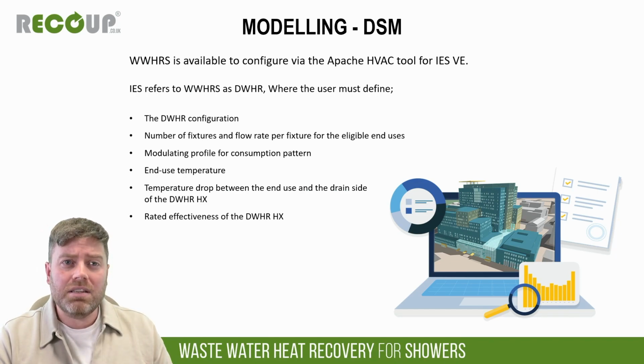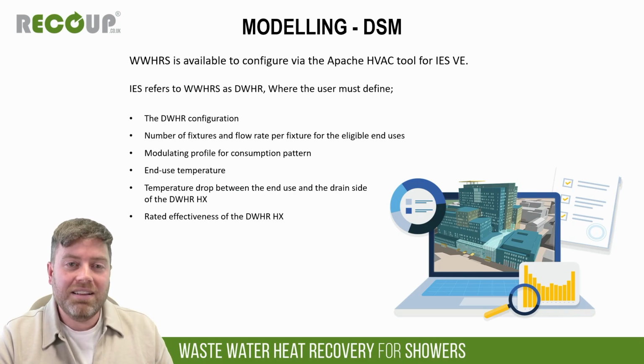In there, you need to specify the number of fixtures and flow rate per fixture for the eligible end uses, the modulating profile for consumption pattern, end use temperature, the temperature drop between the end use and the drain side of the domestic DWHR heat exchanger, and the rated effectiveness of the DWHR heat exchanger. So it is in the add-on if you have it.